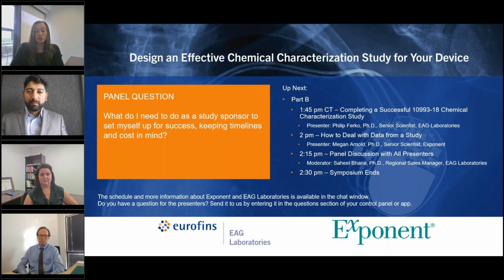Yes, I think anytime you're trying to cover the biocompatibility endpoints that are long-term and systemic. So if you have a device with prolonged or permanent contact, again, considering cumulative exposures, repeated exposures, then you should consider that you're probably going to have to do chemical characterization. I've seen requests lately from FDA reviewers, even for limited contact, short-term contact, even surface contacting devices.